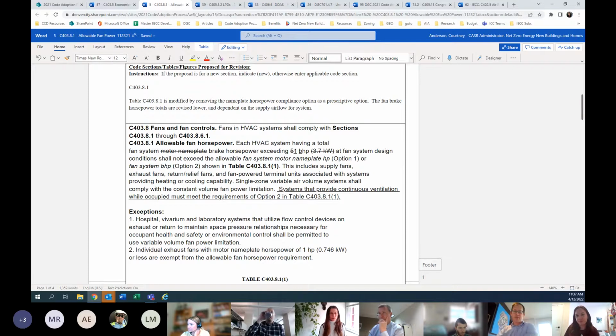Okay, yeah, this is good as a starting point. So this is one of the other major areas for these types of unitary or package systems, where we were looking to see if we could improve the energy efficiency and strengthen the requirements. So there's 2 types of changes here, and both are with regards to the system fan power for systems. So this would apply essentially to both constant volume and variable air volume systems, small and large.